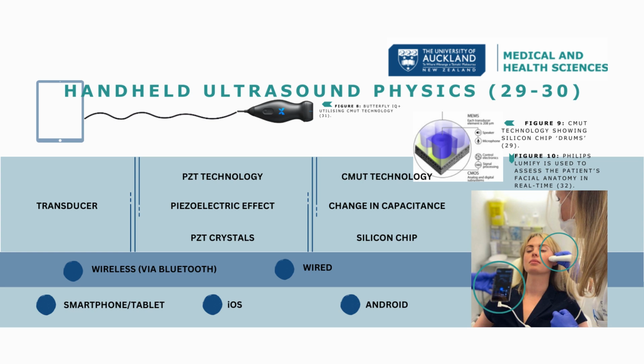With CMUT technology, different frequencies can be applied and no backing material is required, unlike conventional ultrasound probes, thus rendering it more lightweight. Both CMUT and PZT offer high-quality images. CMUT offers a wider bandwidth, thus a wider range of frequencies. However, it does not rely on the crystal sizes and shapes, unlike PZT.